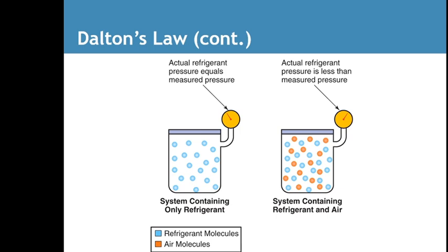And if that continues to happen, sooner or later, you're not going to have a true mixture of 410A. The heavier molecules will still be in the system. The lighter molecules will usually rise out of the system. So at a certain point, you have to remove all the 410A that's in there because it's not pure 410A at that point. Fix the leak and recharge it with 410A, which will give you a proper charge. Because if you keep adding 410A to a leaky system, sooner or later it's not going to work very well because you're losing all the lighter volume refrigerants.